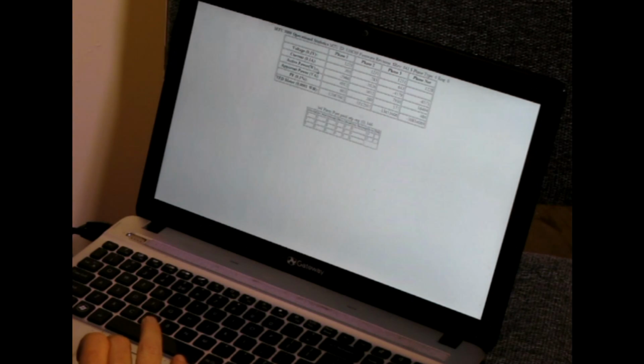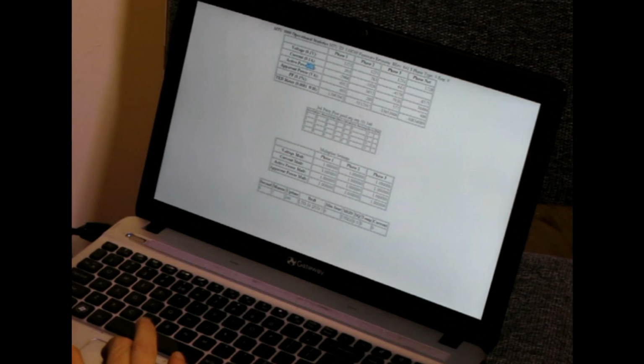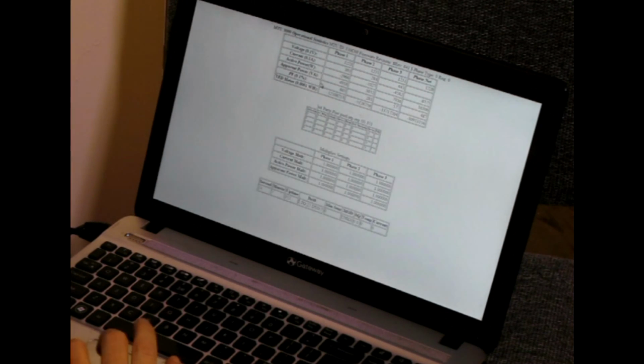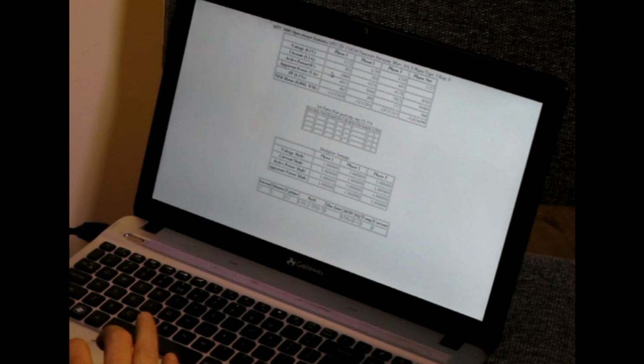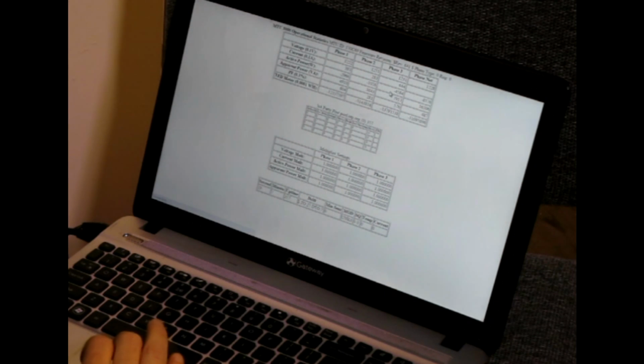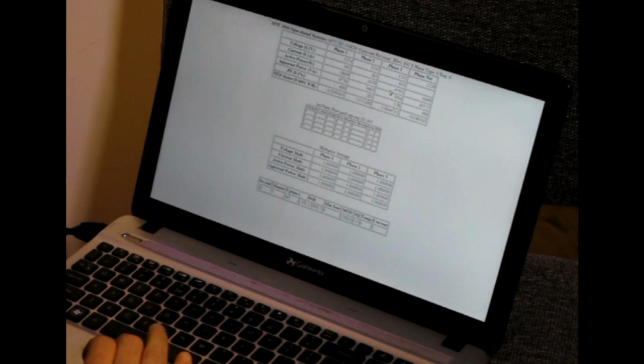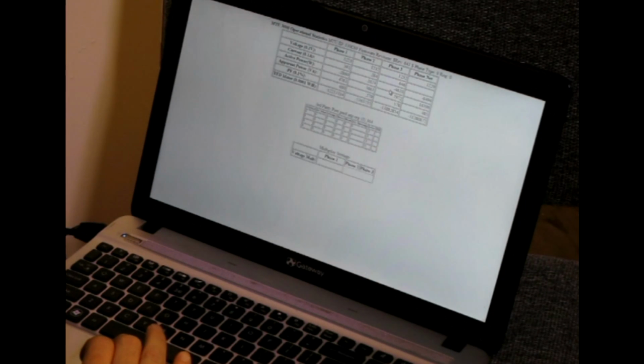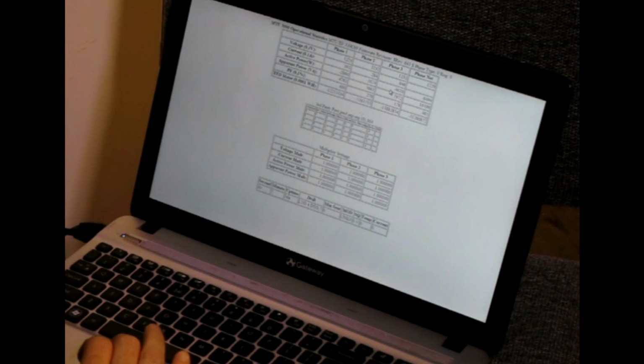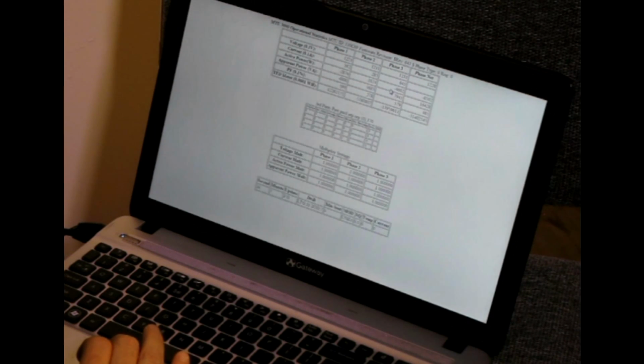What we're concerned with right now is the active power and the PF. As long as you're on a system that doesn't have generation on it, active power should be a positive number. If you see a negative number here, that could indicate two things. Either the CTs are turned in the wrong direction, or the MTU's power cord connections are not matched up A, B, and C phase to the CT connections A, B, and C phase, and they need to be.